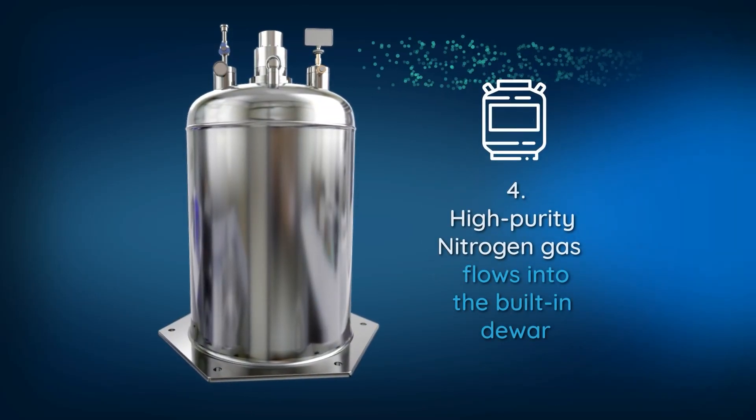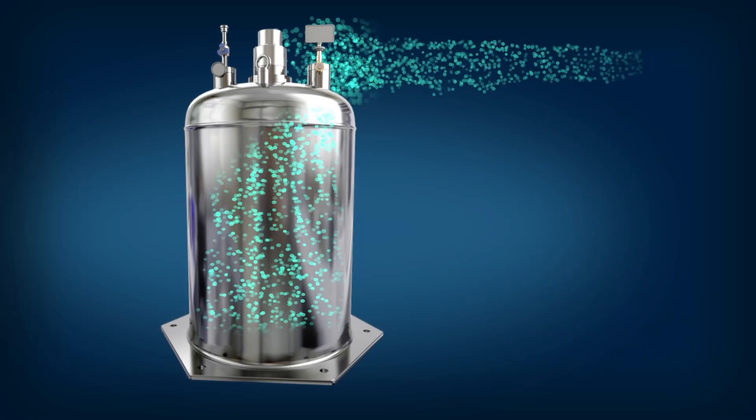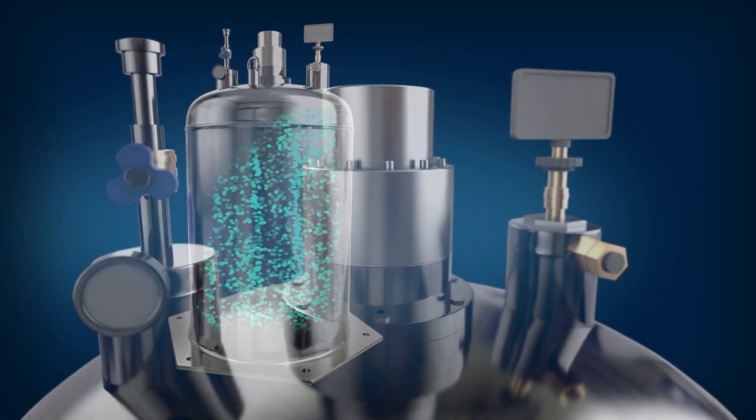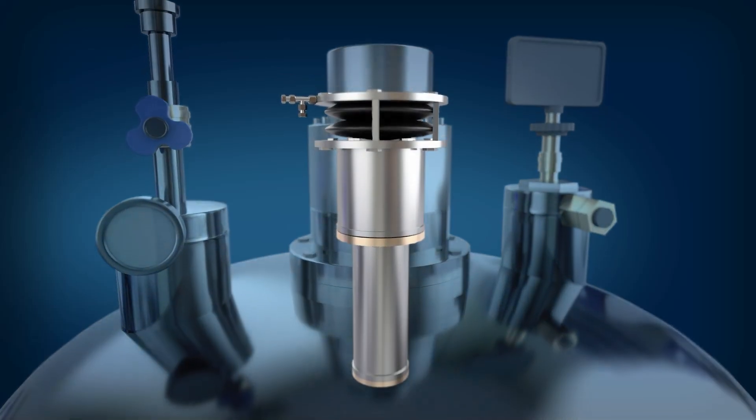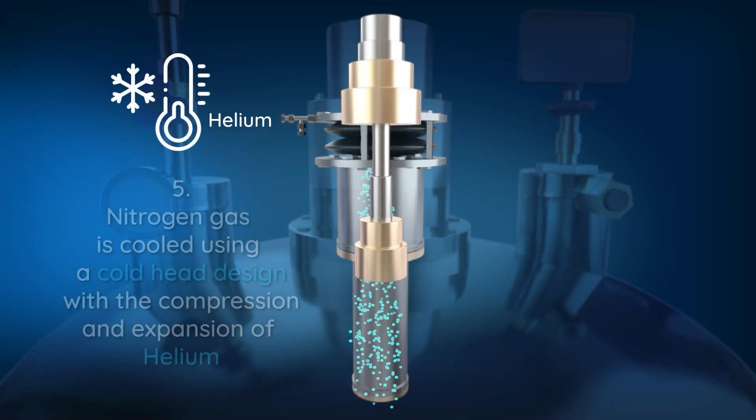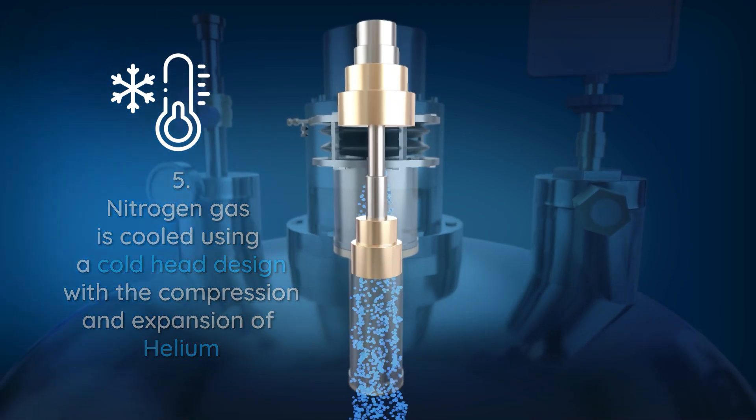High-purity nitrogen gas flows into the built-in dewar. Use of Gifford-McMahon technology achieves low-temperature cooling with helium. Nitrogen gas is cooled using a cold-head design with the compression and expansion of helium.